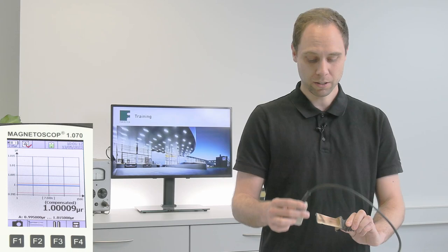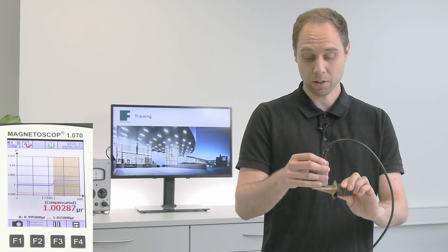If our part is smaller or has a curved surface, we can do a comparative test. So we can measure the part on this position, but we have to make sure to measure always in the same position.